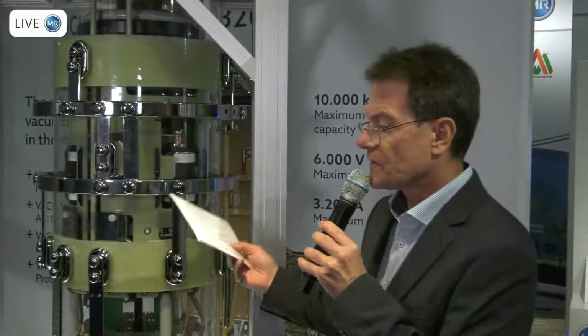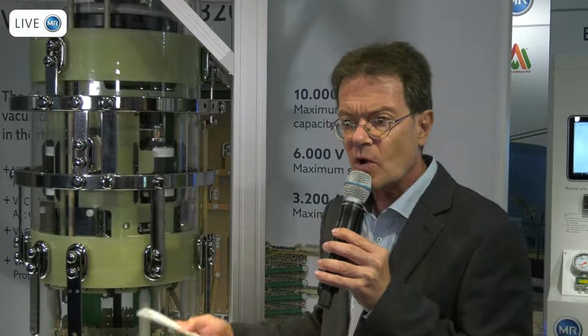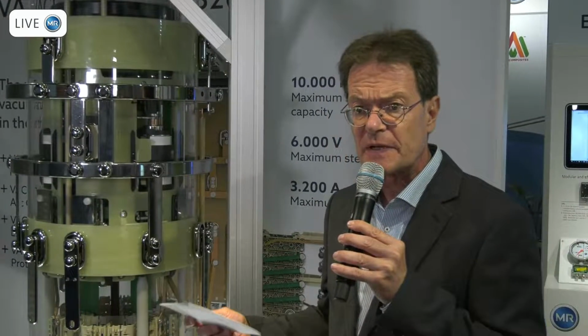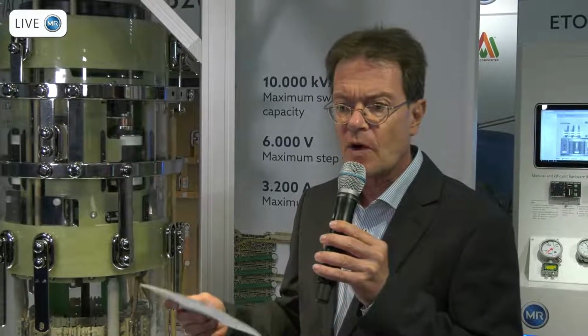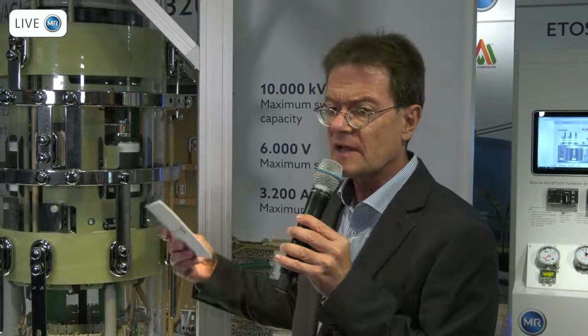When we talk to transmission operators, one of the keywords we hear is availability of the transformer and, of course, sustainability. Which advantages come along with the VRL? The VRL offers, with a 3200 amp nominal phase current, the option in almost all cases that there is no more need for a symmetric current split in the regulating winding, and that means less space, less material, less weight, and even lower switching losses. So a lot of advantages for the grid operator over the lifetime with the VRL in the phase shifter.